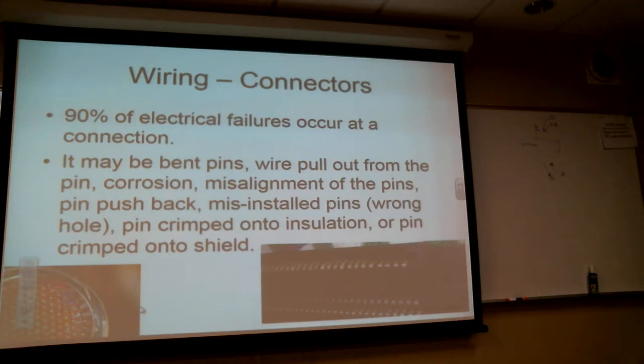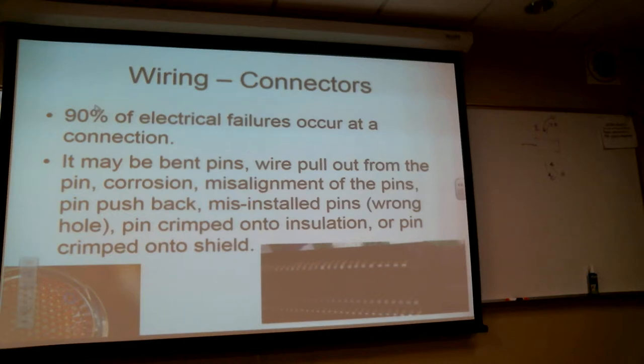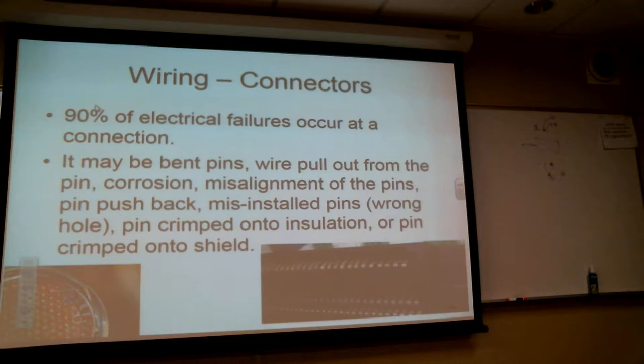This is where you're going to make your money — easy money. That number I gave was conservative; it's probably more like 99% of all electrical failures occur at connections. Even ones where a load device or other device is damaged often occur because an electrical connection was bad.